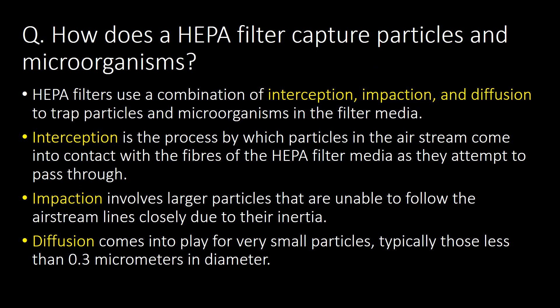How does a HEPA filter capture particles and microorganisms? HEPA filters use a combination of interception, impaction, and diffusion to trap particles and microorganisms in the filter media. Interception is the process by which particles in the air stream contact the fibers of the HEPA filter media as they pass through. Impaction involves larger particles that cannot follow the air streamlines closely due to their inertia. Diffusion comes into play for very small particles, typically those less than 0.3 micrometers in diameter.